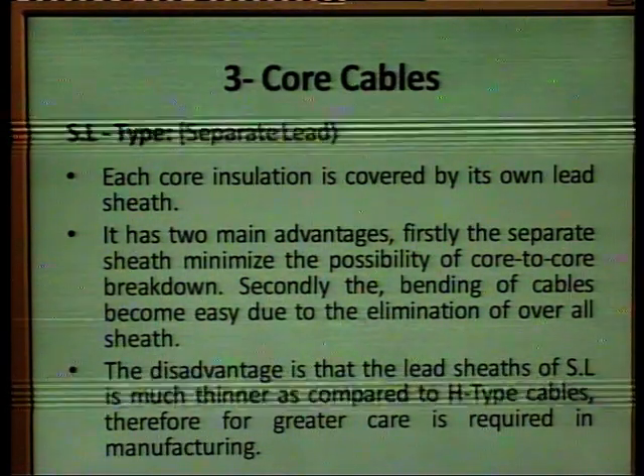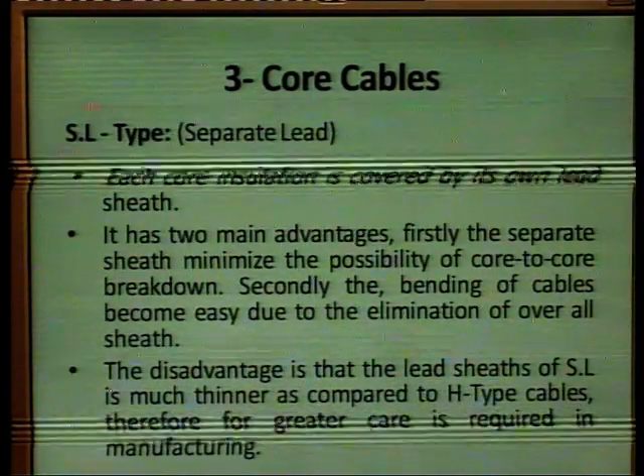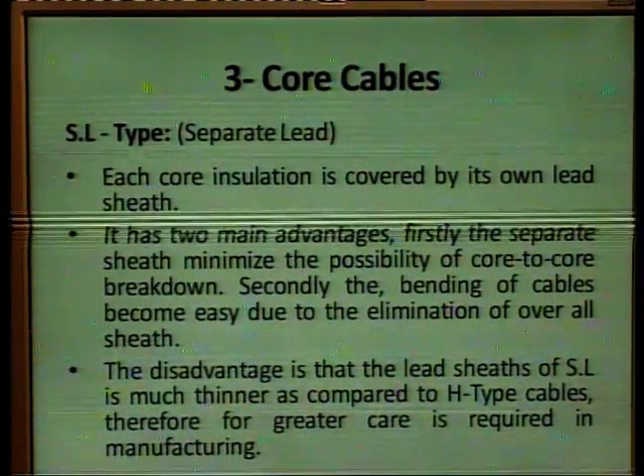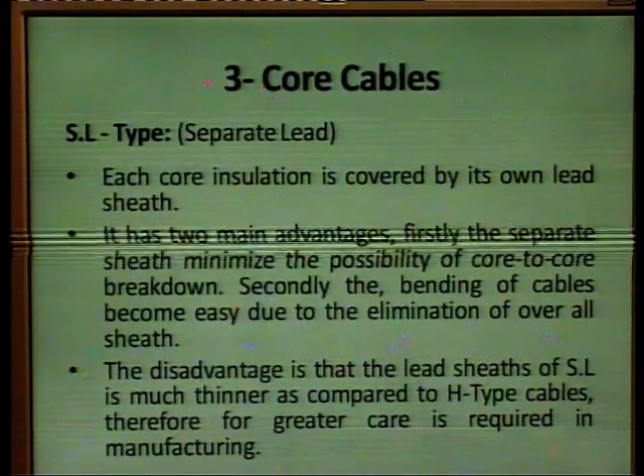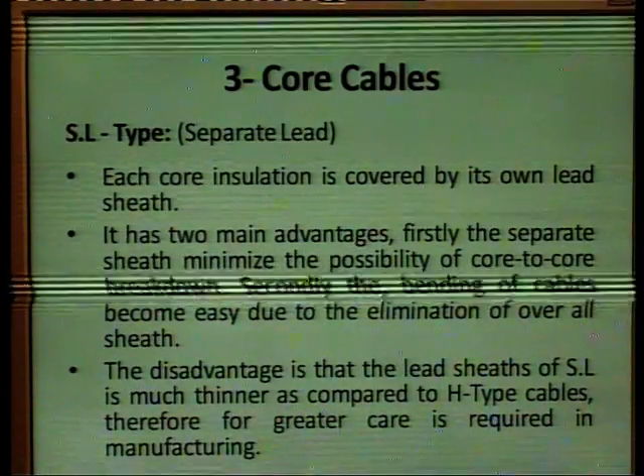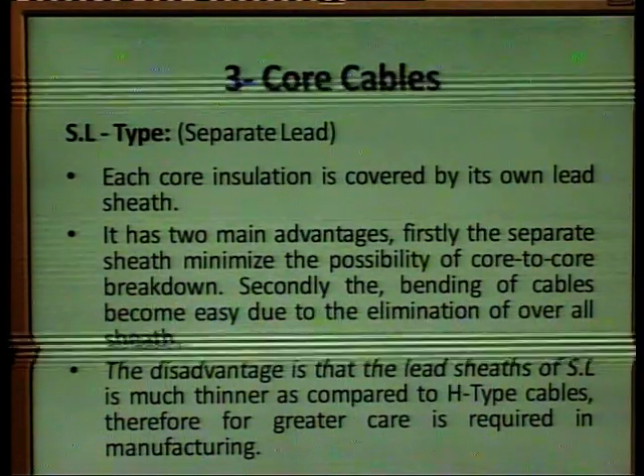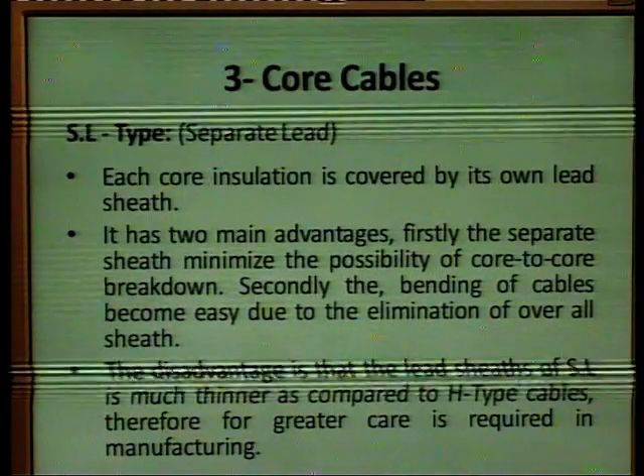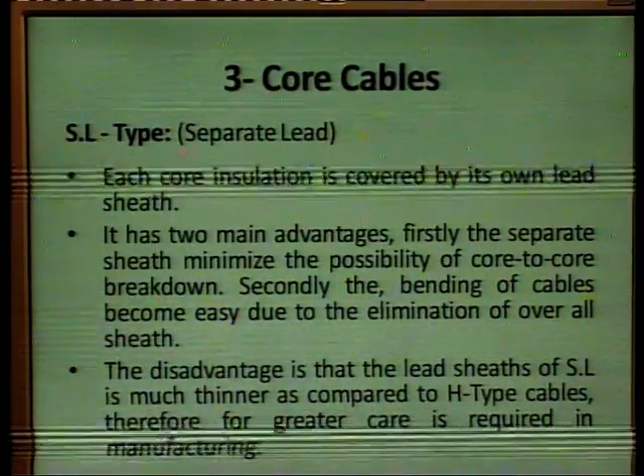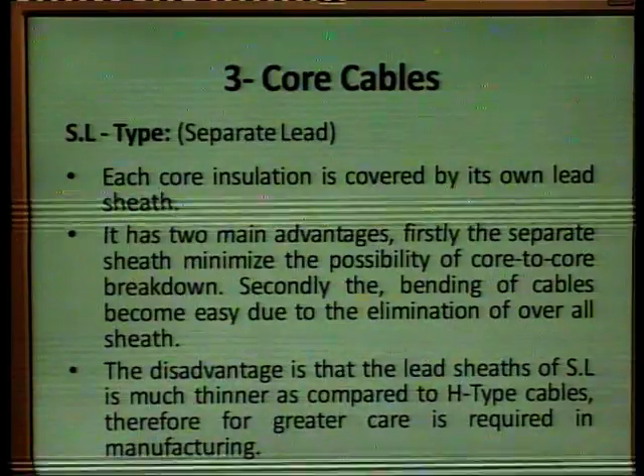Then we have 3-core cables of SL type, known as separate lead type. In this type of cable, each core insulation is covered by its own lead sheath. It has 2 main advantages. First, the separate sheath minimizes the possibility of core to core breakdown. And secondly, the bending of the cable becomes easy due to the elimination of the overall sheath.